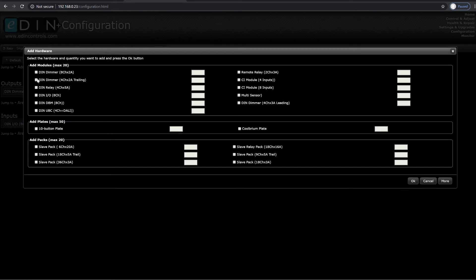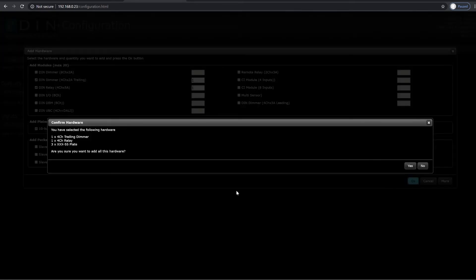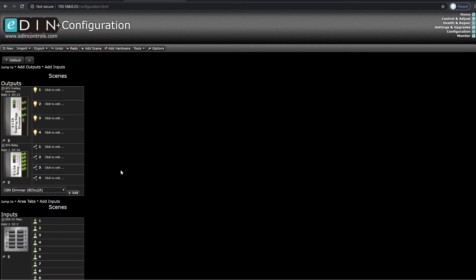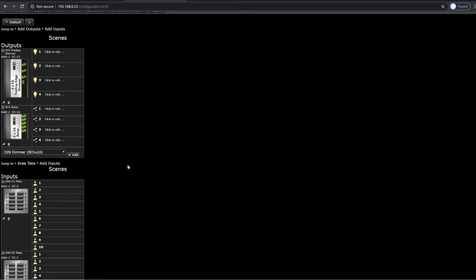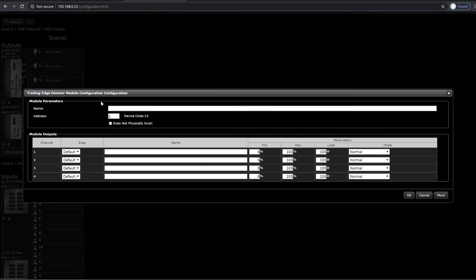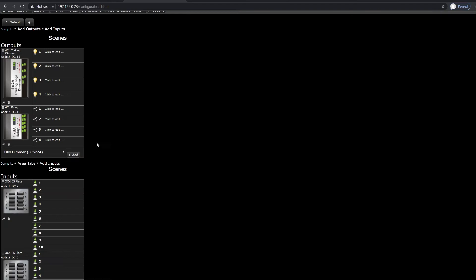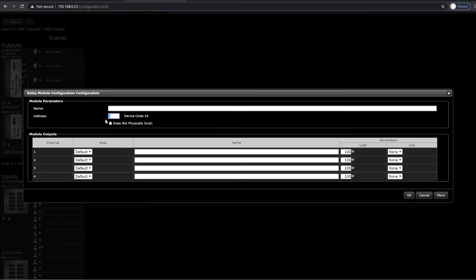In this example, I have a trailing edge module for mains dimming and a relay module for switched channels, along with three ten-button keypads. Once I've selected that hardware, I can press OK and it will ask, are you sure? I'm going to say yes, and then all of this hardware is added below. We need to make sure that our modules are on the addresses that are actually scrolling on the front of the screens of the modules. In this case, my modules are not on these addresses, so I'm going to change them — this one will be on address two and my relay module will be on address three.